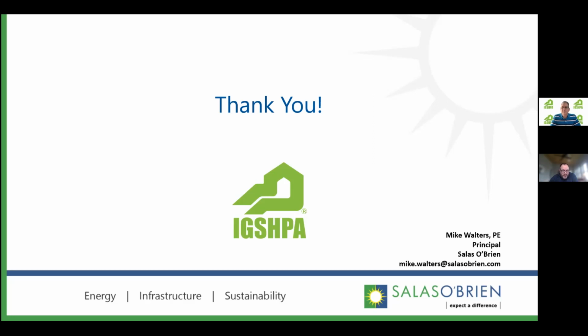That's what happened at Ball State. When a building turned red, it was because the supply hot water temperature was reset down to 145 degrees, and either the control system flagged it through monitoring, or an actual person called and said their space was no longer warm enough. So in almost all of our existing campuses, we ask for slow supply water reset until the building systems tell you they can't hold space temperature anymore—that's where we draw the line.